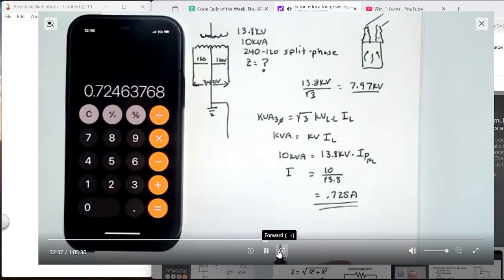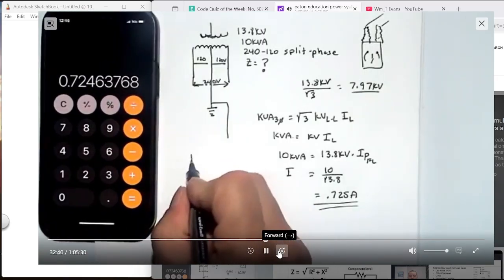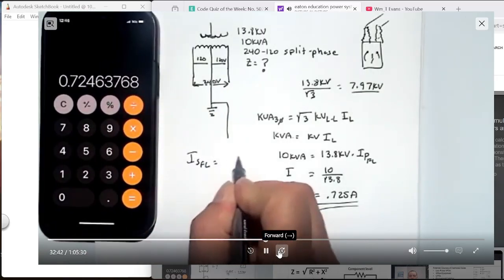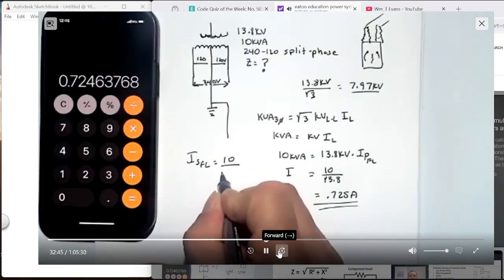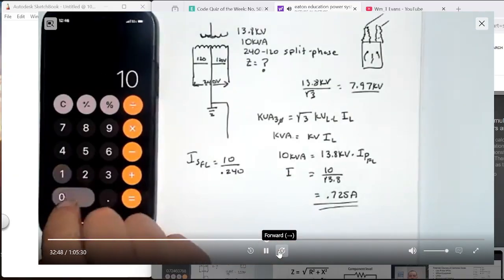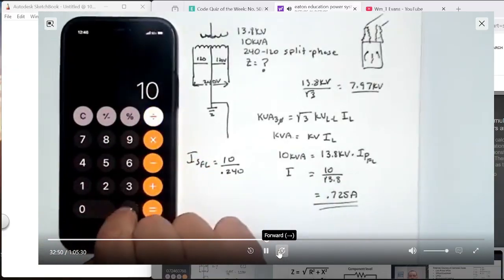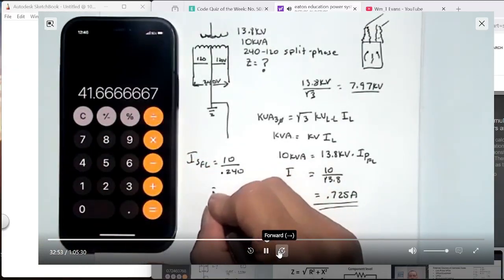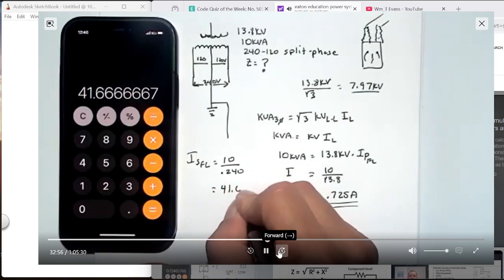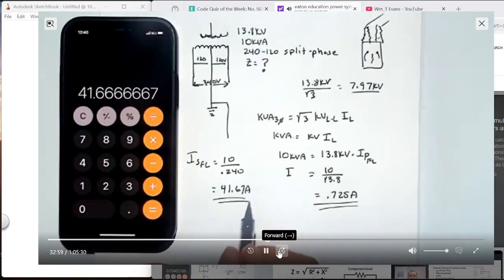The other part about this that's cool is if you look at the secondary, secondary full load, we have 10 kVA divided by 240, so 10 divided by 0.24, and we get about 42 amps, 41.67 amps. So for obvious reasons, then we put 200 amp panels in, or we put multiple 200 amp panels in our house, right? What's cool about this, when you think about it, our panel in our house is 200 amp, but we can only supply 41 amps or 42 amps from the utility transformer based on its capacity.